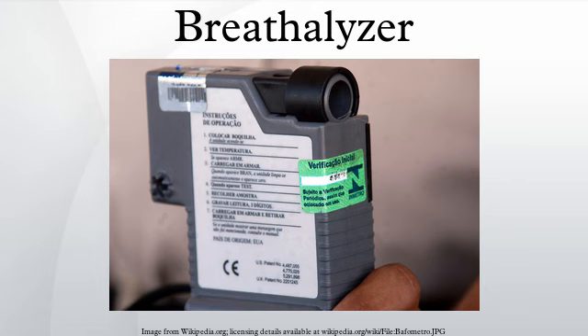Many handheld breath analyzers sold to consumers use a silicon oxide sensor to determine the blood alcohol concentration. These sensors are far more prone to contamination and interference from substances other than breath alcohol, and require recalibration or replacement every six months. Higher-end personal breath analyzers and professional-use breath alcohol testers use platinum fuel cell sensors, which also require recalibration but at less frequent intervals — usually once a year.